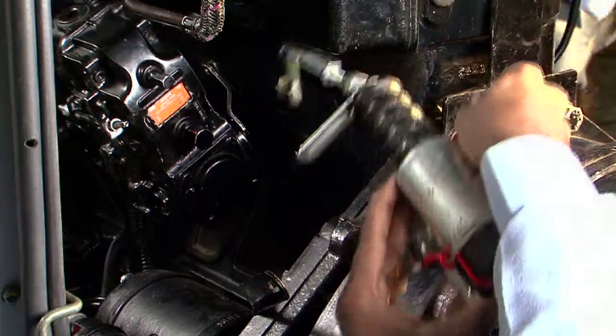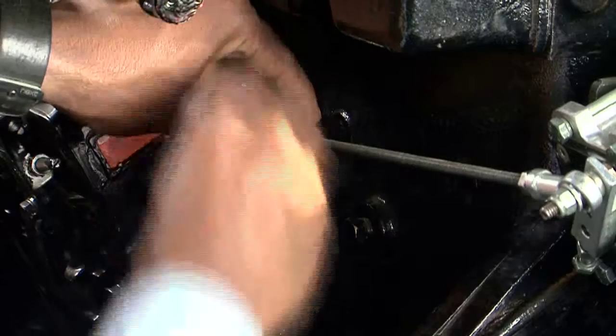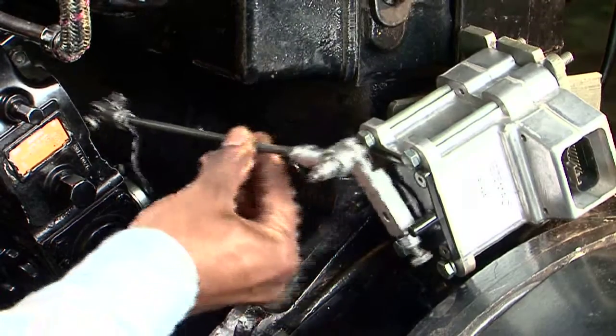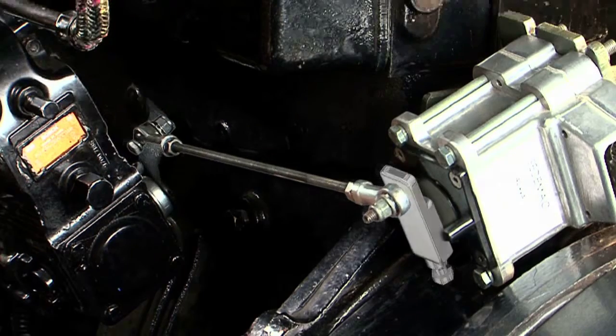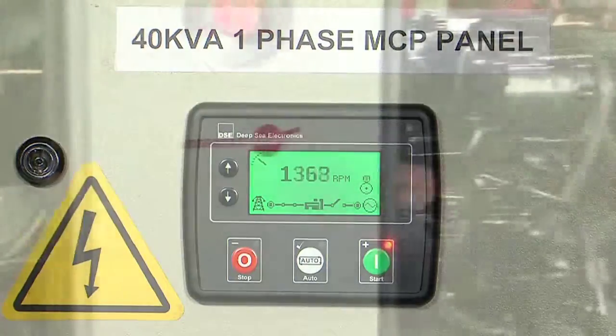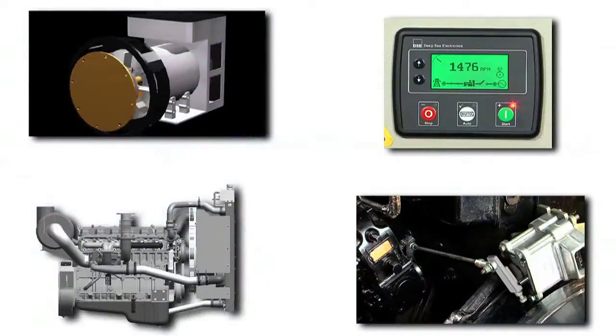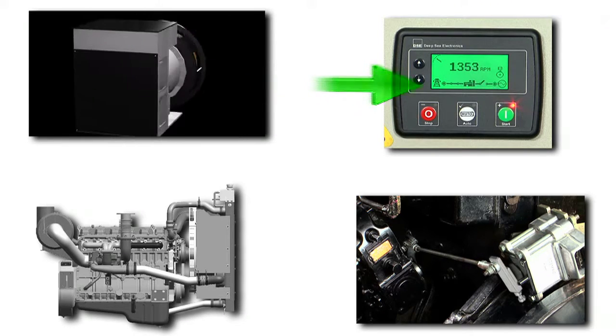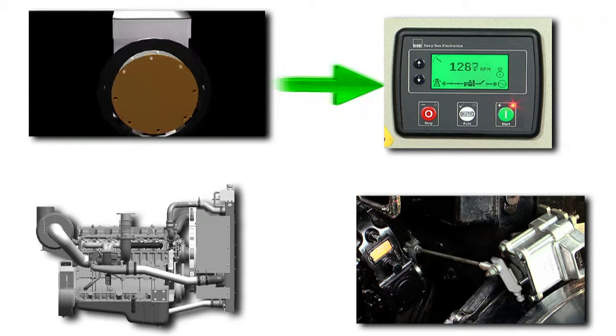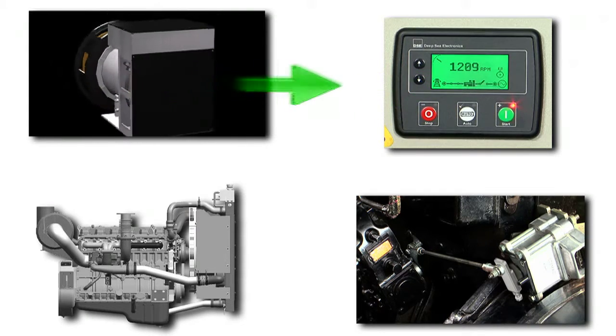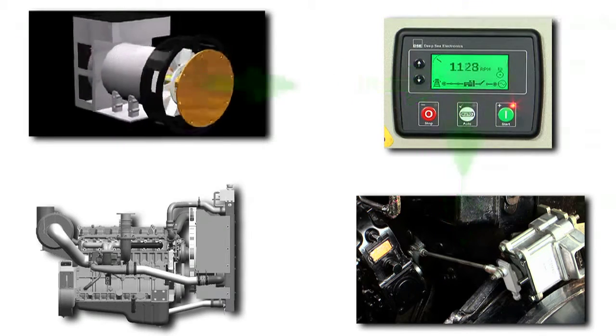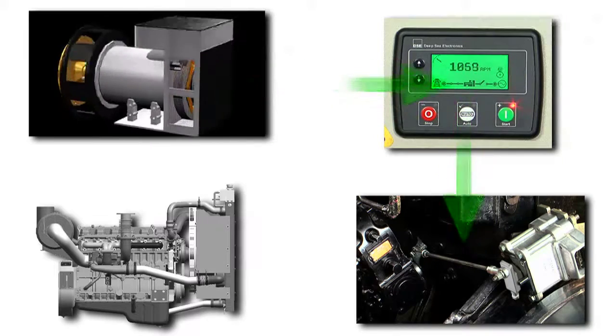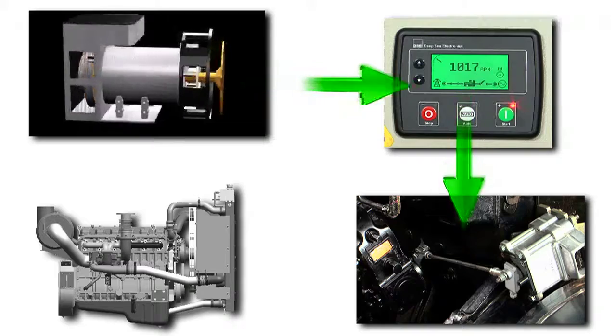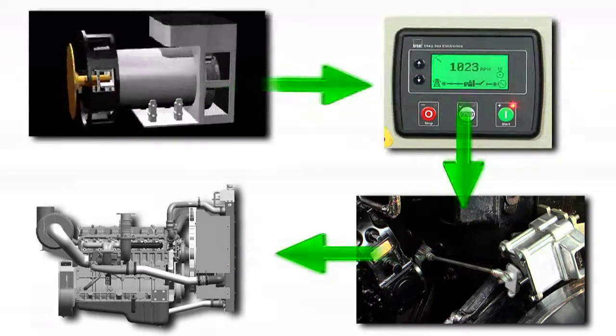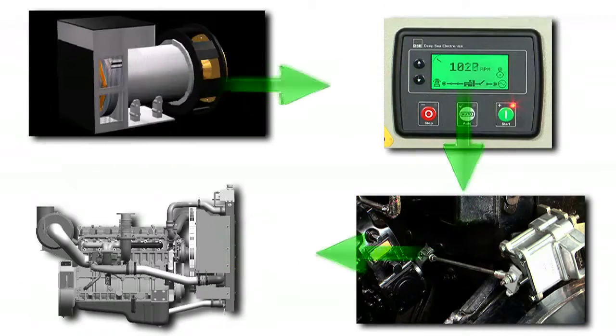The I-18 actuator replaces the stop solenoid of the engine. The actuator is connected to the FIP stop lever to regulate the fuel flow into the engine and thereby have a control over the engine speed. When the genset is in operation, the control panel continuously senses the DG load and sends the load signal to the I-18 actuator. Based on this load information, the intelligent I-18 actuator continuously calculates the optimum engine speed suitable for the measured load. Accordingly, it controls the FIP lever to achieve the optimum engine speed. As a result, the genset speed varies based on the load, and the fuel is saved.